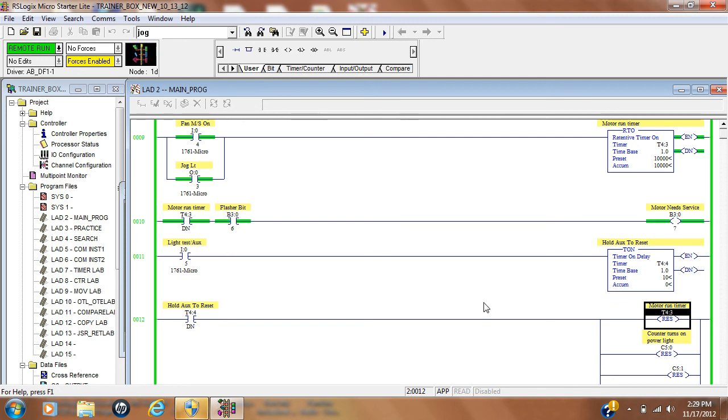So what I need to do is I have a little button here I'm pushing. I need to push this button for 10 seconds and watch what happens over here at 10 seconds. At 10, the done bit went true, and I'm still holding it, by the way. And this went and it reset our accumulation value up here. Now if I release it, we can actually see exactly what happened there. Our fan motor starter's on, the retentive timer is timing. Now if I stop the motor, see it's going to hold that 14. Start the motor, and she keeps going.